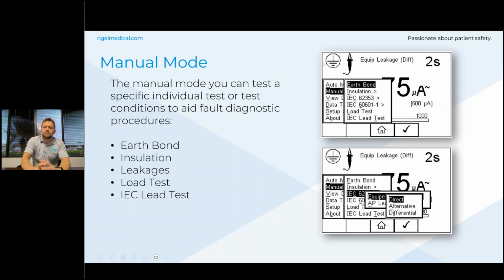The 288 is a manual and automated tester. So from the menu settings, you can go through all the different manual tests, but it's preferably used as an automated tester because it's got test sequences in there for storing results, and it does work better as an automated analyzer. But you do have manual mode there as well for doing any fault finding and doing any manual tests just for measuring the different leakages, ground bonds, or insulation tests.